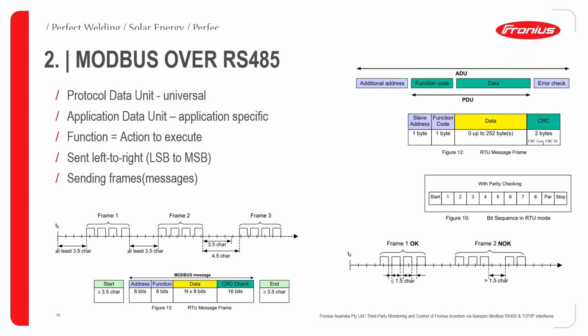A lot of times we have questions about whether we can integrate over Wi-Fi, or other media. You can. You need to start thinking of how that would interface the gaps in between the bytes and the frames. For example, if the gap is too long, it's usually not an issue unless you split individual bytes, then the slave and the master will discard the frames.